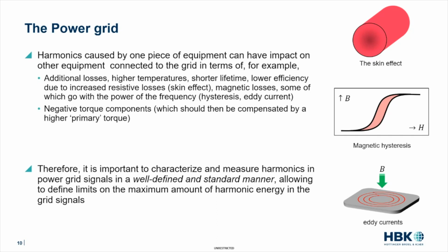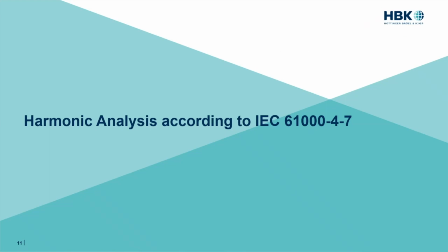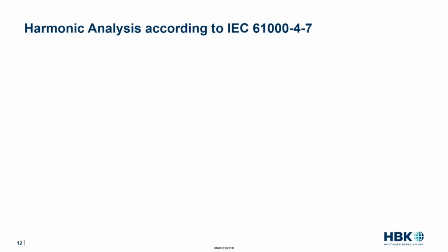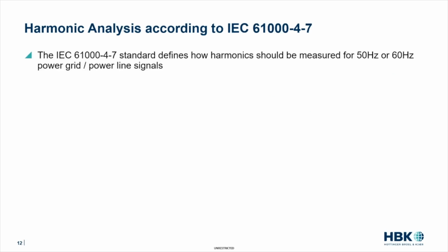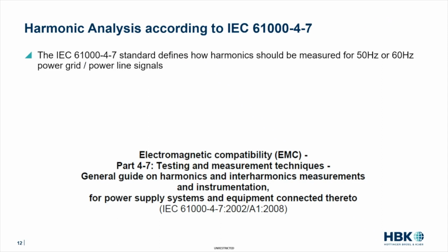And basically, the IEC 61000-4-7 standard does exactly that. So what does this standard define? The IEC 61000-4-7 standard defines how harmonics should be measured for 50 and 60 Hertz power grid or power line signals. So it tells you how you should measure those harmonics. This is the total official title of that standard: testing and measurement techniques, a general guide on harmonics and interharmonics, which I will talk about later, measurement and instrumentation for power supply systems and equipment connected thereto. So it is really targeted at power grid and power line signals.